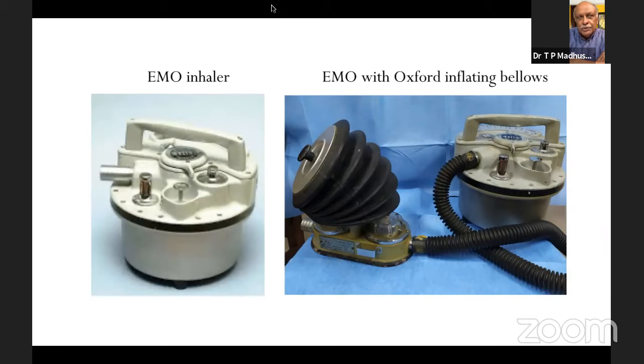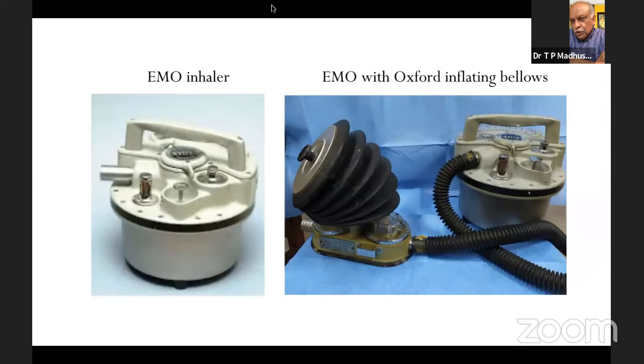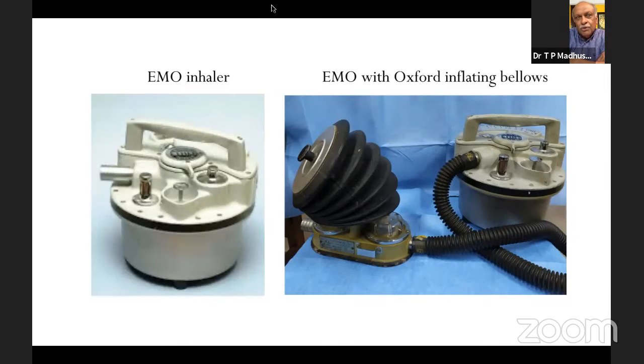The original concept was to use it only as an ether vaporizer, but subsequently a scale was developed for trilene use, and later a modification was made for methoxyflurane. A problem at higher altitude was lower oxygen partial pressure, requiring oxygen supplementation. Brigadier Ram of the Indian Armed Forces developed a Ram Rao adapter for oxygen enrichment at the inlet of the EMO apparatus. EMO performance and qualities have remained a gold standard for a long time. Unfortunately, the non-availability of ether has resulted in it being relegated to a museum piece.